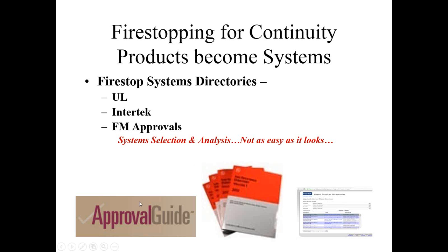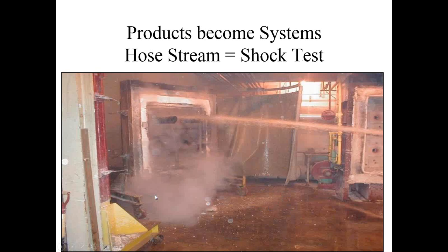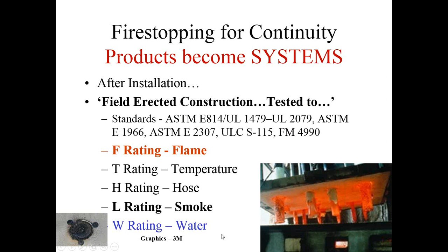Key things to remember: the time-temperature curve when fire testing these assemblies is 0 to 1,000 degrees in about 10 minutes and about 1,900 degrees in 2 hours. So it's a pretty rigorous test for the ASTM E814, the UL 1479. Sorry, the ASTM E119, UL 1479.